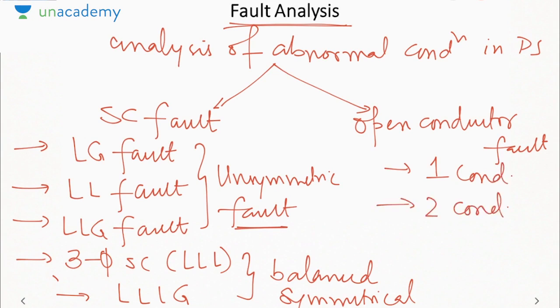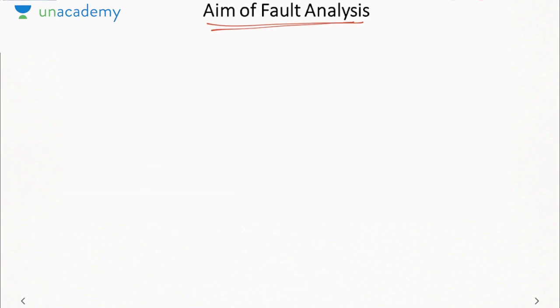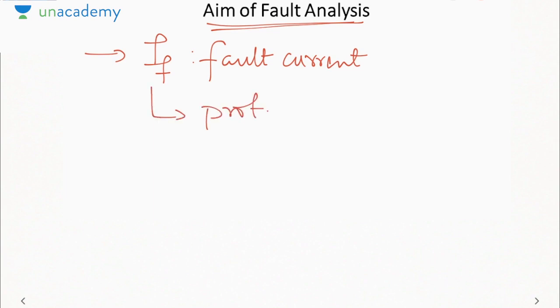But in our GATE scope we have only short circuit faults, so we will take a look at the analysis of short circuit faults. But the first thing that comes to mind is, why are we doing fault analysis? What is the purpose behind it? Why go through so much trouble to arrive at the fault current? The reason is, if we know the magnitude of fault current before the occurrence of fault, then I know how much current will be flowing in the system if a fault occurs. And if I know how much current will be flowing under faulty conditions, then I will devise a measure to open circuit the power system if such a current will flow. That is, if I know how bad the conditions can be in the power system at the time of fault, then we can design an effective protection system.